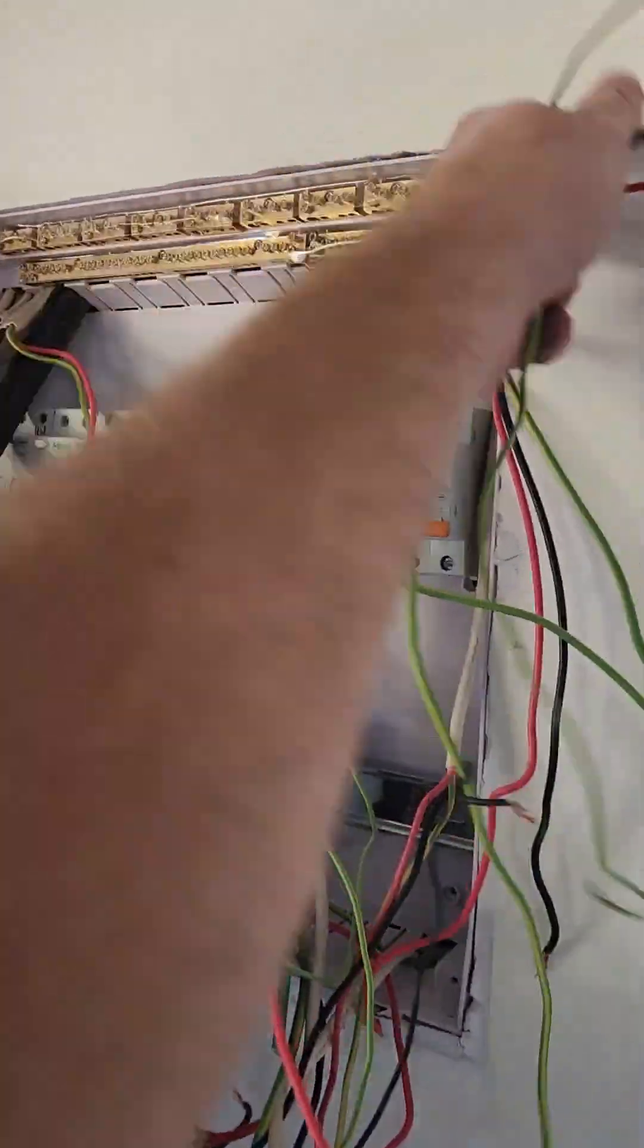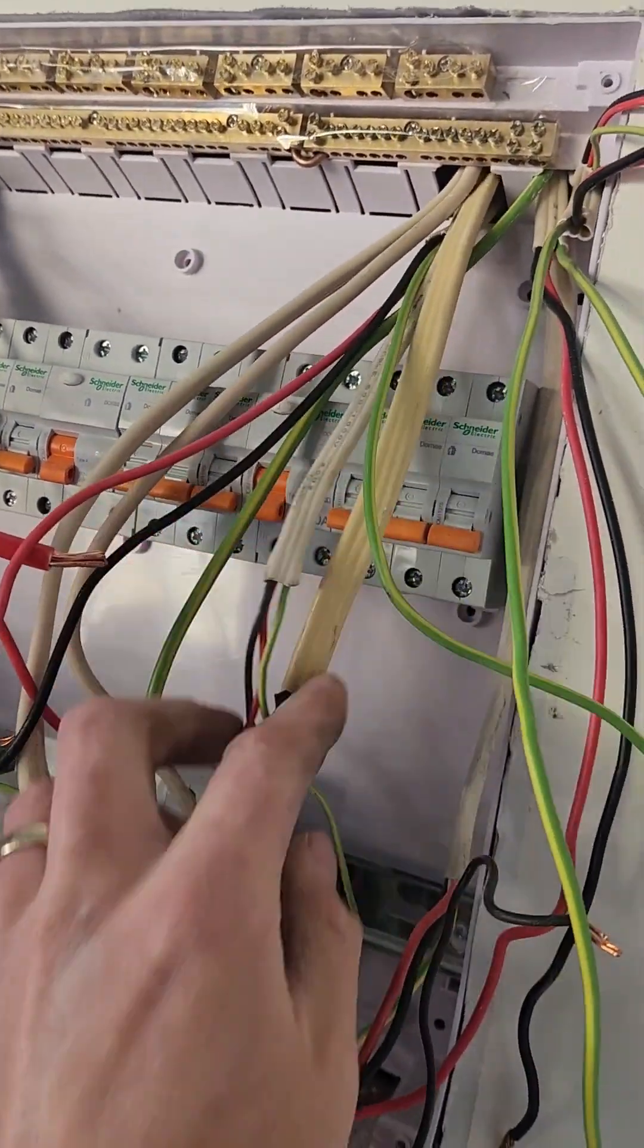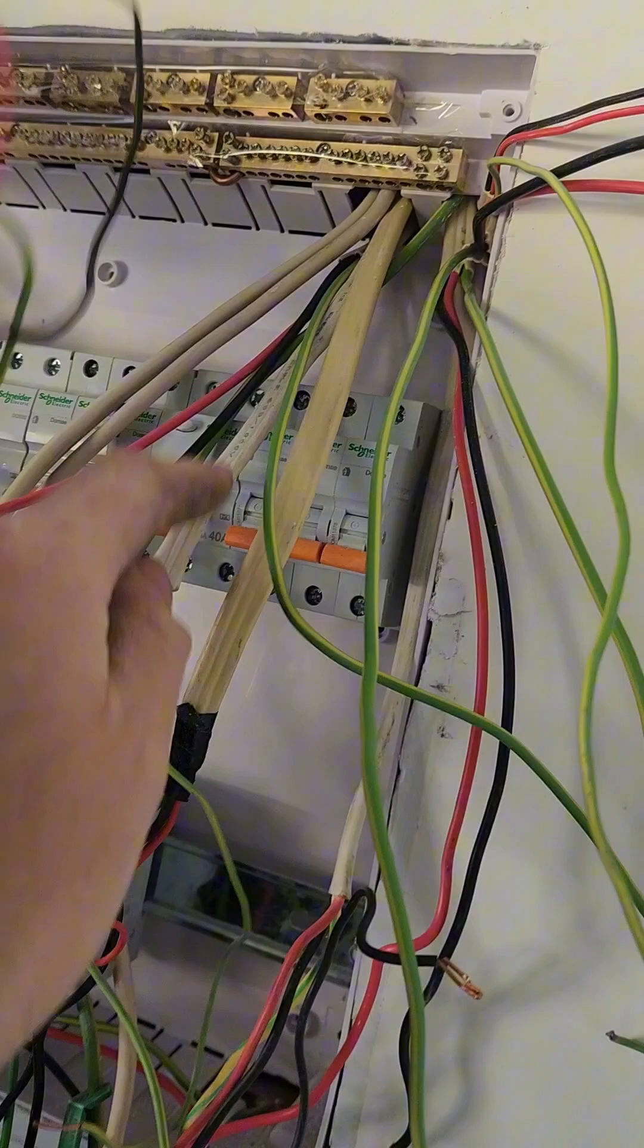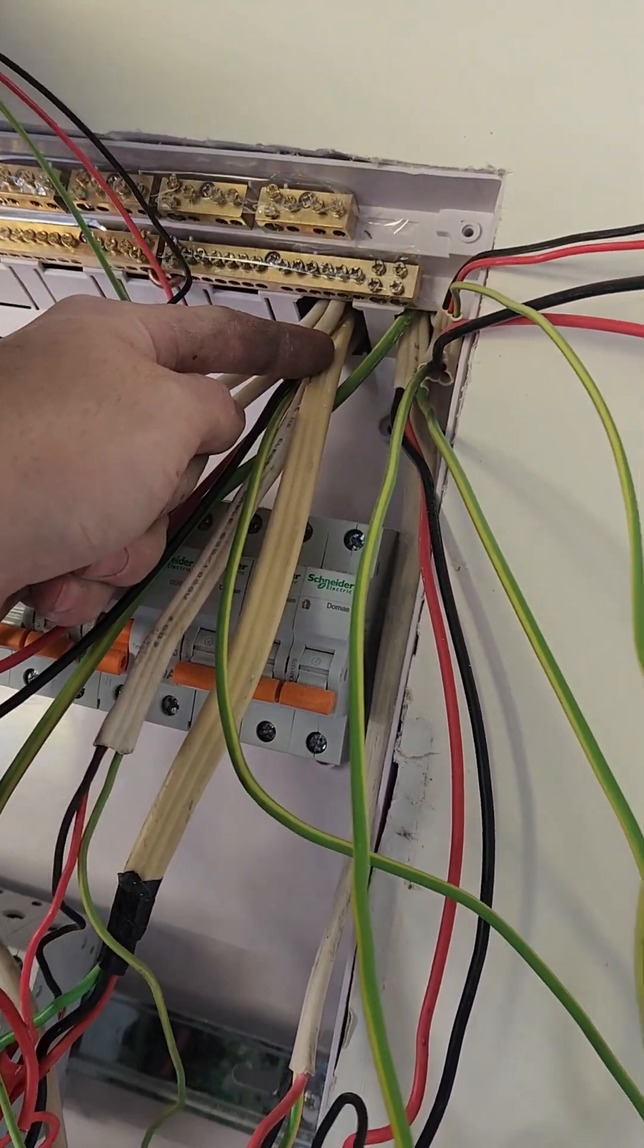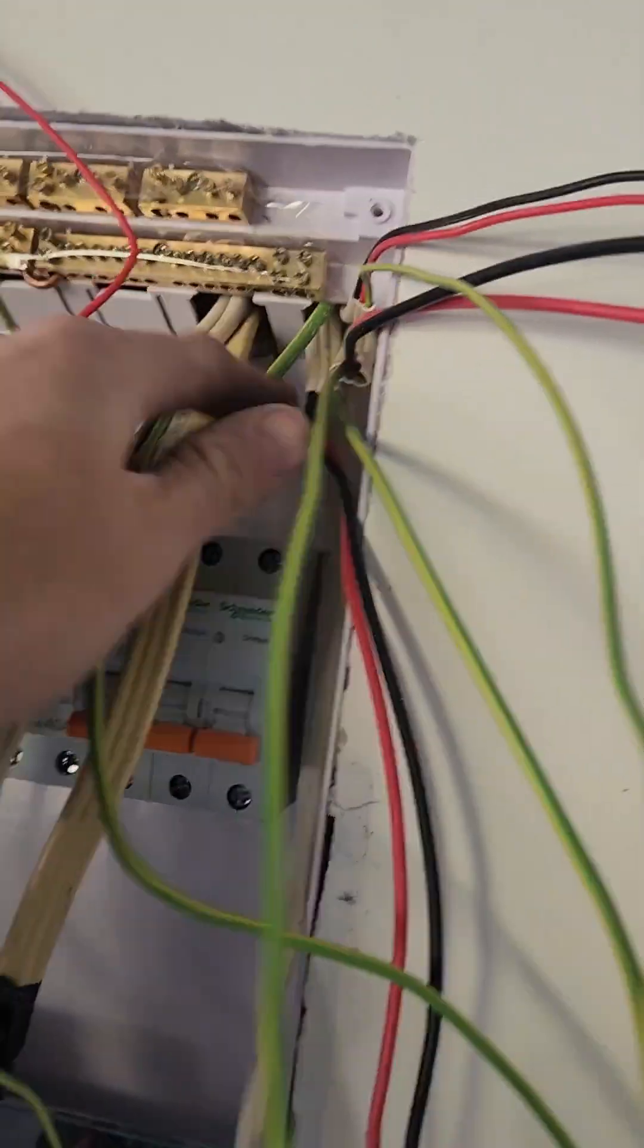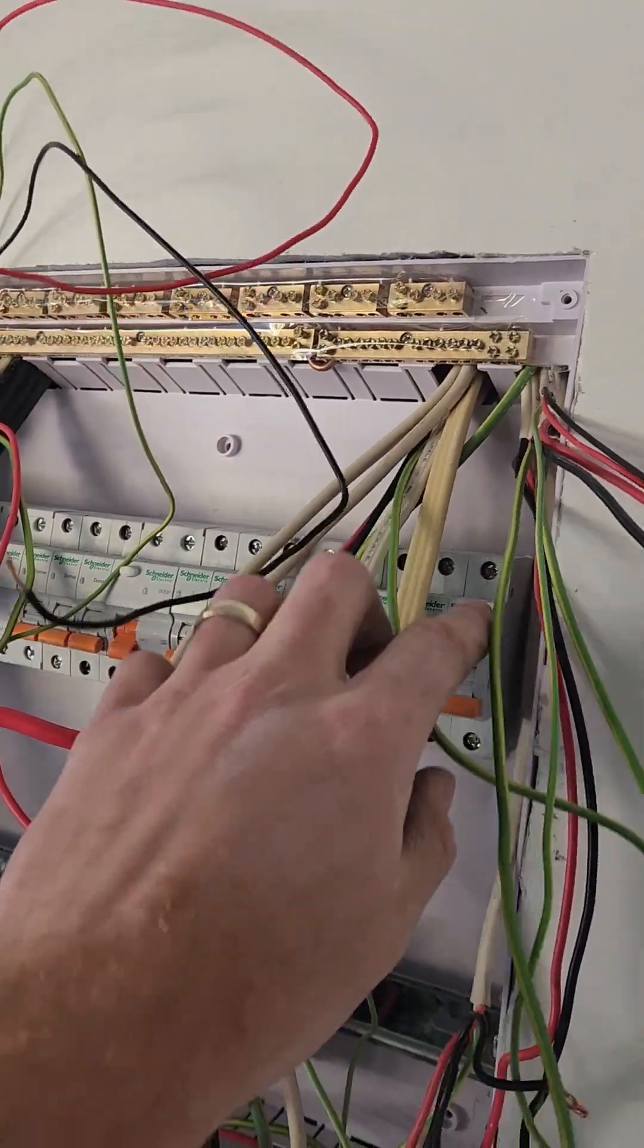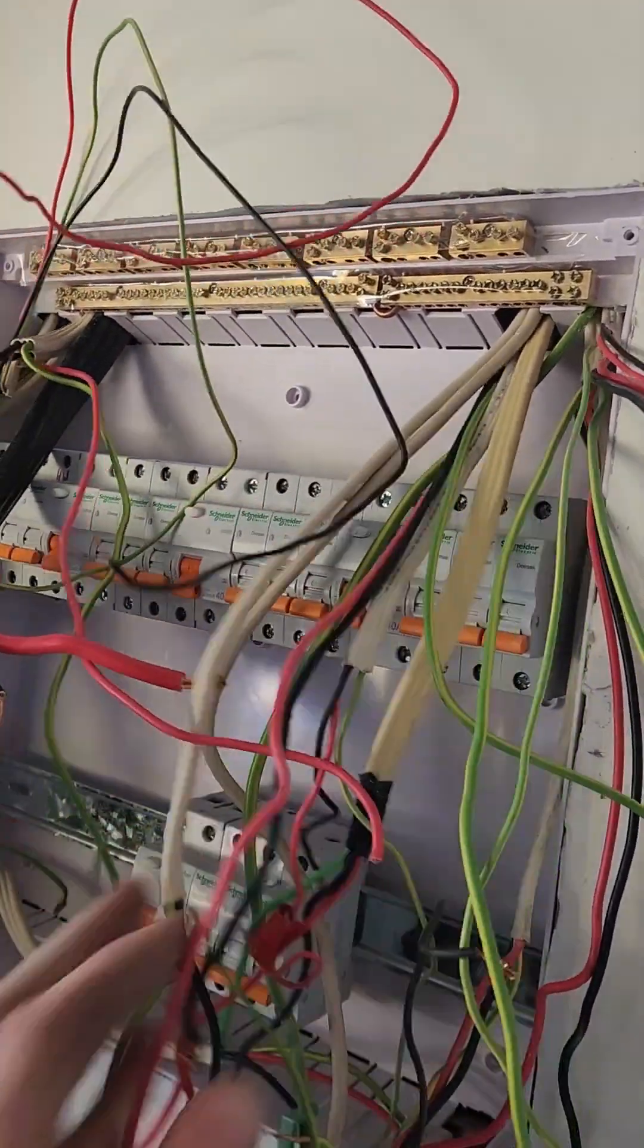Alright so we've got the new switchboard in and now we're just stripping the TPS, which is the white cable. Instead of at the old switchboard location we're stripping it up to here where it enters the board. Basic insulation can't be in the roof space so we have to stop just shy like these ones here. We'll get those stripped up, we'll make the earths off and then we'll start making the neutrals and the lives off.